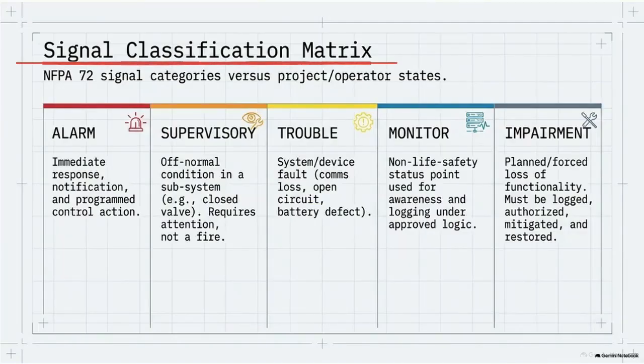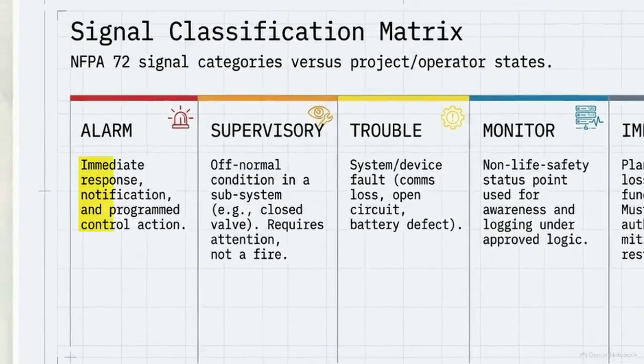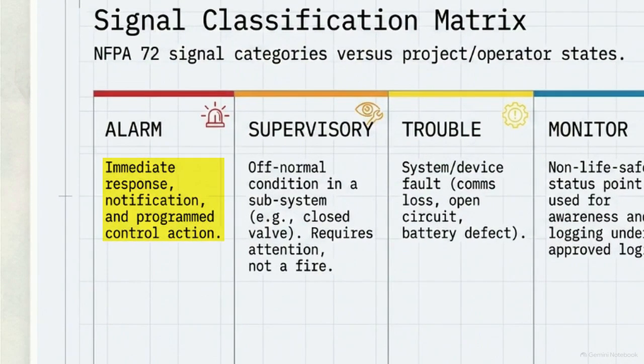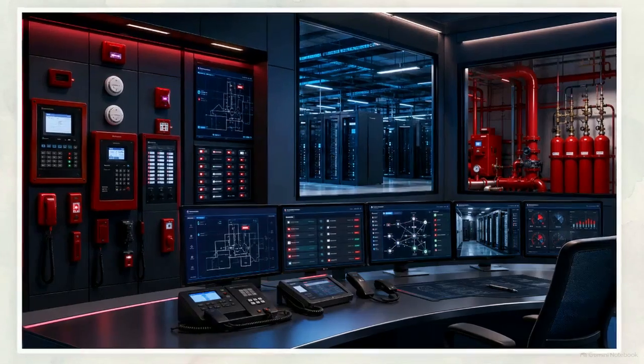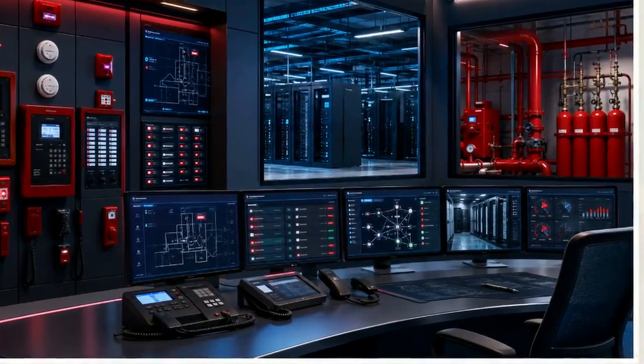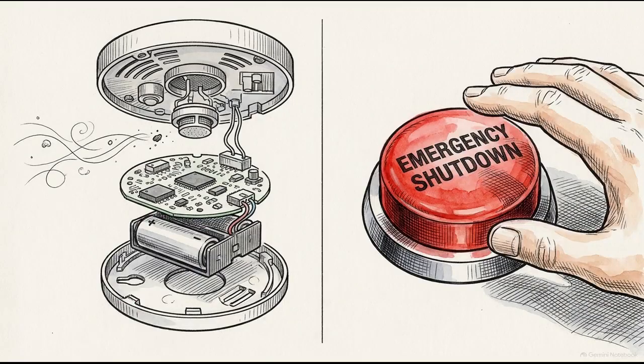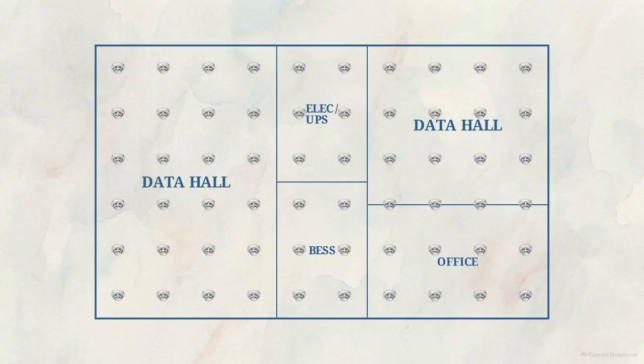Looking at this classification matrix, we see how the system prevents panic by separating incoming data. Red alarm signals require immediate emergency response, while orange supervisory signals indicate off-normal conditions in subsystems, like a closed valve, that require maintenance but not an evacuation. Data center reliability rests on operators trusting these distinct signals. If the system creates ambiguity between a dirty sensor and a fire, humans often make errors in judgment that lead to unnecessary shutdowns. Effective fire protection avoids the trap of a generic blanket strategy applied evenly across a floor plan.